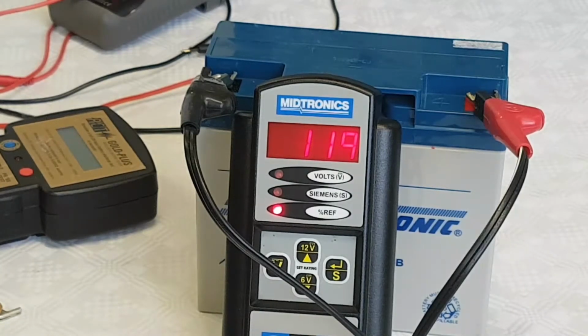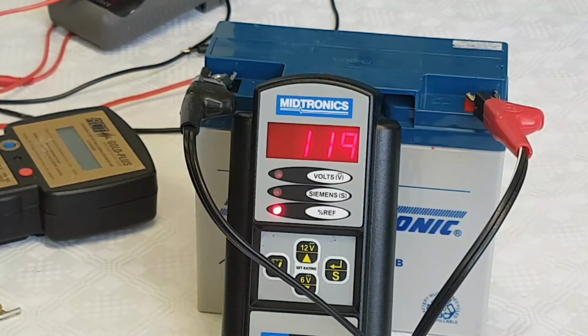So a reading of less than 60% is indicative of a battery that has reached the end of its useful service life. You can see therefore the Midtronics test is a far more superior tester, and provided you have the appropriate reference values, which are available from the battery manufacturer or the Midtronics website, any brand of battery can be tested.